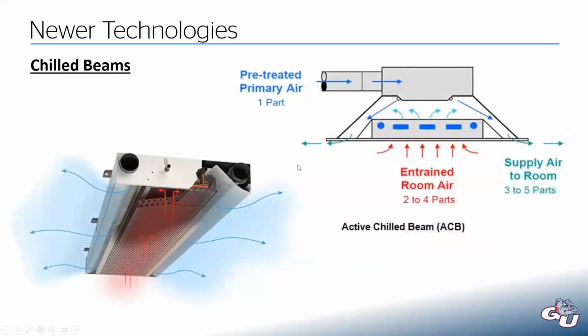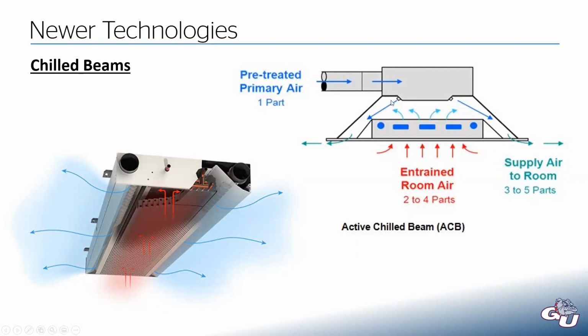So this is more of a section view of what this looks like. Here's our primary air, which is coming from a DOAS unit. And then it enters this, I guess I'd call it a plenum, where it pressurizes as it's trying to force its way in. And then you have these tiny nozzles that force this air to discharge at a very high velocity. And if you're blowing this air at a very high velocity, the Coanda effect will induce some air to follow suit. It'll pull it along because that air is moving so fast. The adjacent air is going to come along for the ride.